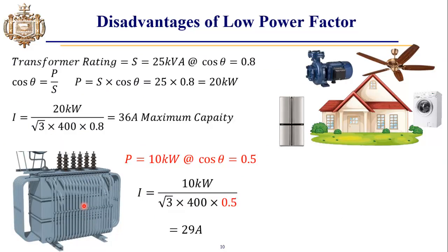This is a distribution transformer which is providing electricity to the residential area. The rating of this transformer is 25 kVA at cos θ equal to 0.8. So we can compute the total active power which this transformer can provide according to this formula, which comes out to be 20 kilowatts. The maximum current that this transformer can provide comes out to be 36 amperes according to this formula.